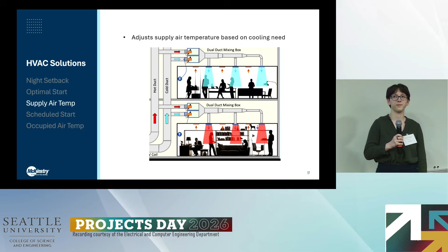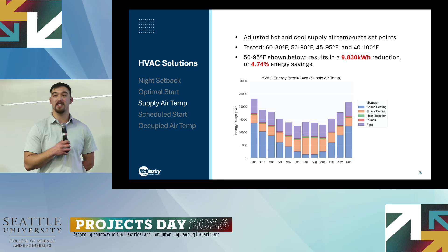For supply air temp, we tested more and less extreme values. These values with higher delta T, or difference in temperature, resulted in more energy savings. So we chased this until we ran up against the ASHRAE 55 guidelines. So we settled at 50 degrees of cold air supply and 95 degrees of hot air supply. These would be then mixed in a variable air volume damper that would be then put into the room. So you won't be blasted with 95-degree air. This resulted in a 10,000 kilowatt hour reduction in energy usage, which is about 4.7% energy savings.